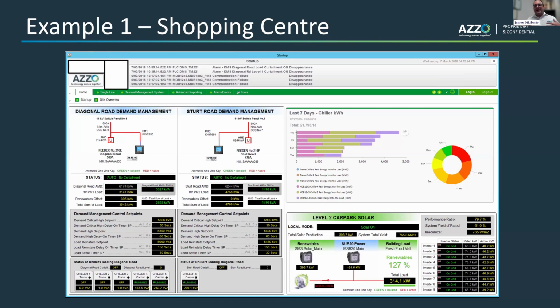This took advantage of the building envelope and made sure that the loading and unloading of the chiller management system on site was done in such a way that it could avoid having to upgrade the transformer for those rare times. As the previous presenter showed on the duration curve, you don't actually need that much capacity if we could manage it in a shorter, faster amount of time. And we can.